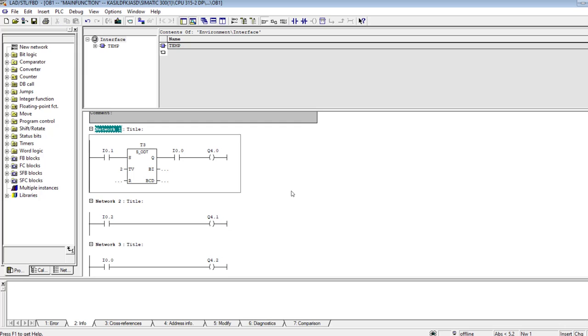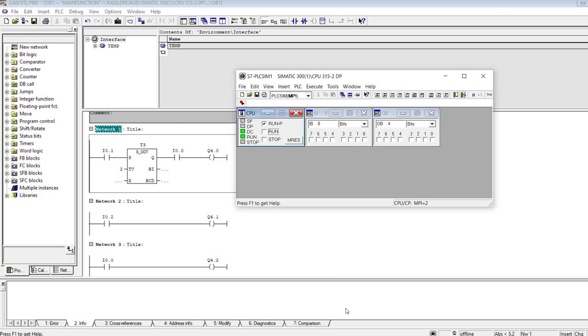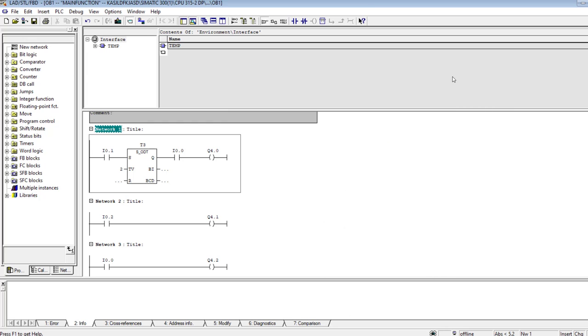So this is a simple modification that I made. Now I want to download this modified program to the PLC without stopping the PLC. The PLC is in the run mode. I have used a simulator, but you can use the hardware. This method can be applied to the hardware as well.